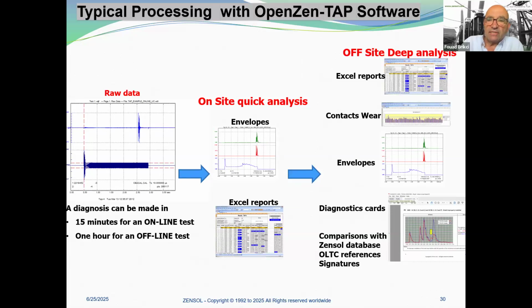First, mathematic processing is done by calculating the envelopes for the current drive and the vibroacoustic signals. At the end of this process, we produce a typical report for each transformer OLTC. On the left picture, you can see the raw data, the motor current on the bottom, and the accelerometer on the top. The diagnosis can be made in 15 minutes for an online test and 1 hour for an offline test.